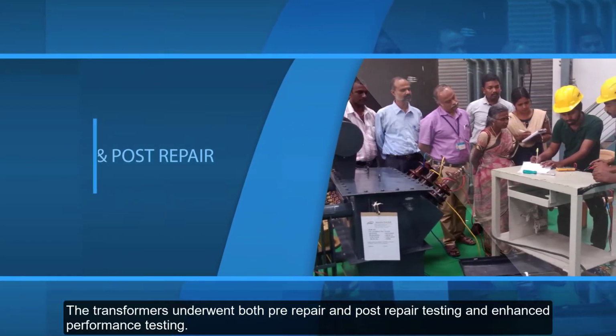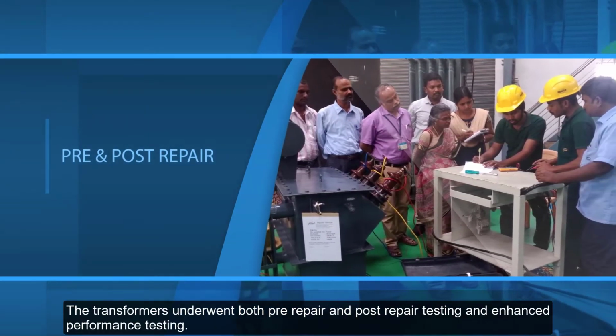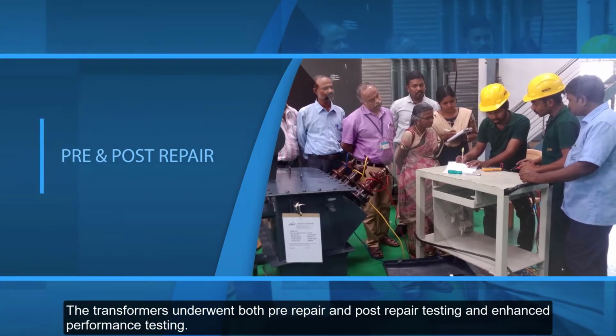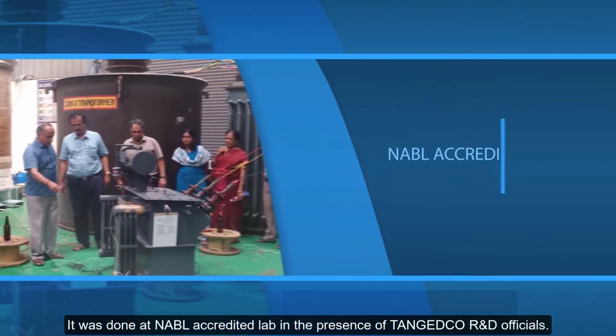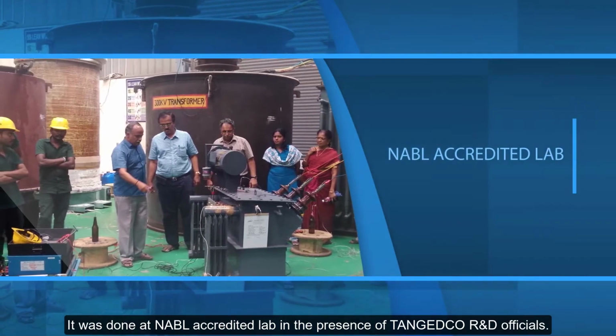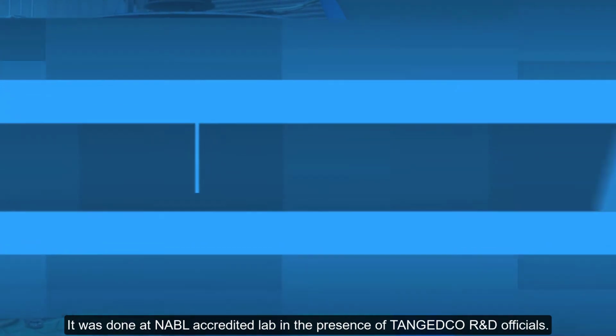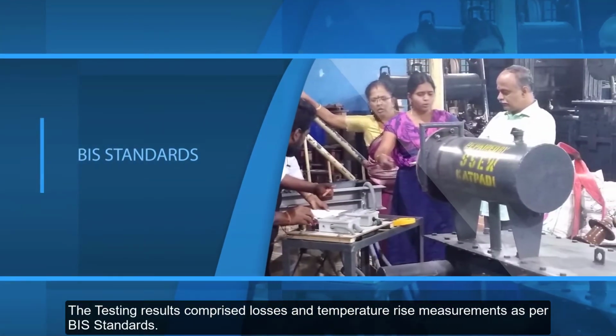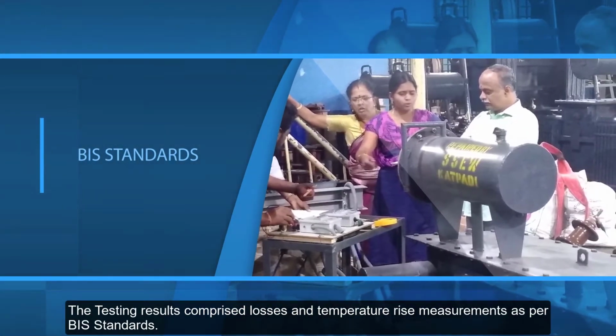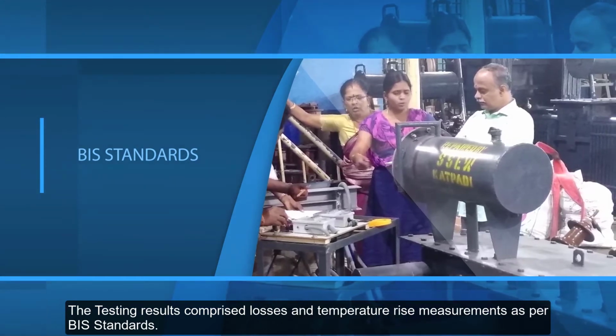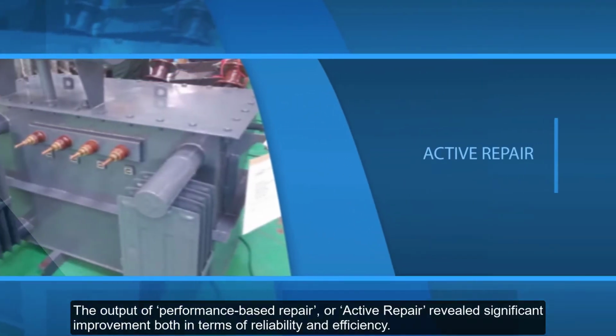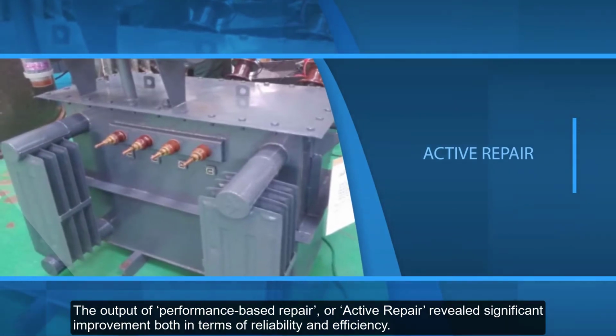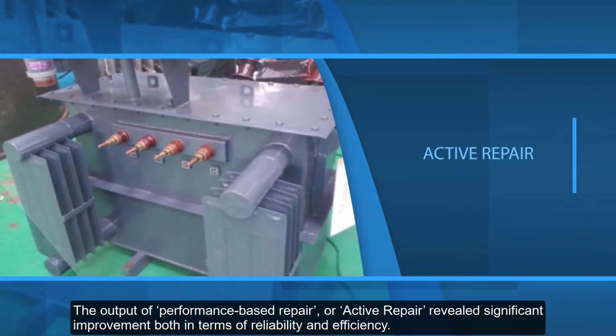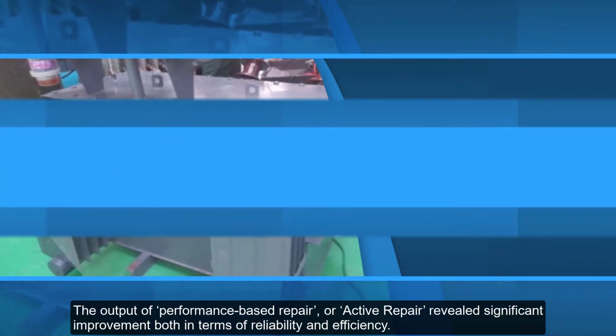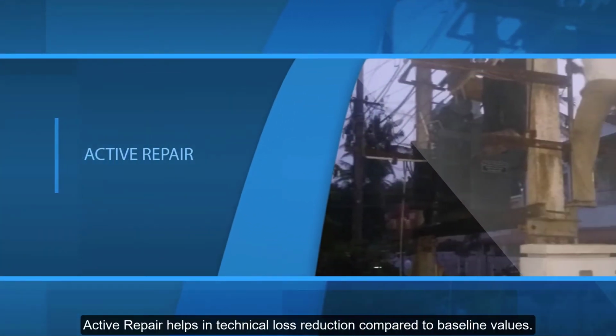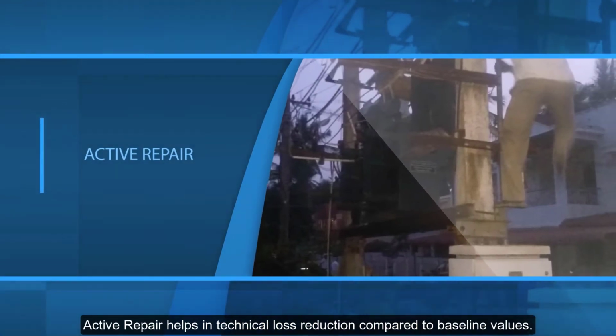During this process, the transformer underwent both pre-repair and post-repair testing and enhanced performance testing. It was done at an NABL accredited lab in the presence of TANGEDCO R&D officials. The testing results comprised losses and temperature rise measurements as per the IS standards to establish benchmark levels. The output of performance-based repair, namely active repair, revealed significant improvement both in terms of reliability and efficiency. Active repair does help in technical loss reduction compared to baseline values.